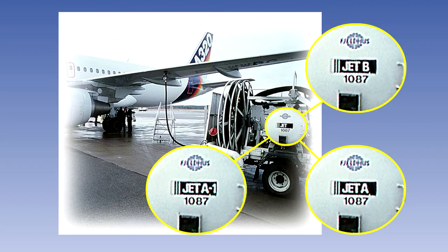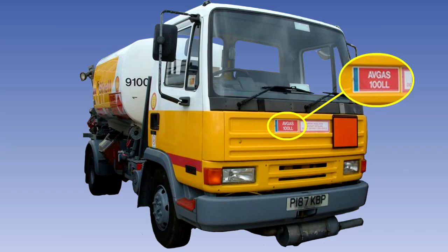Fueling vehicles and hydrants dispensing AVTUR are identified by prominently placed labels with the words Jet A, Jet A1 or Jet B, depending on the grade, printed in white on a black background. Fueling vehicles dispensing AVGAS are identified by prominently placed labels with the word AVGAS and the grade, for instance 100LL, printed in white on a red background.